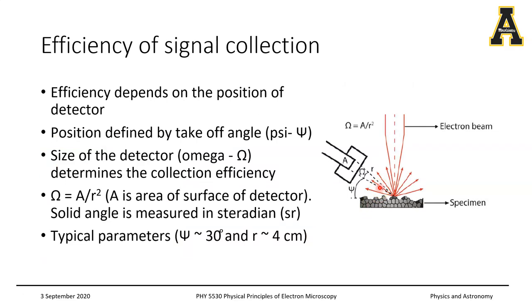Now let's look at the efficiency of signal collection. The tip of the ET detector is positioned at a takeoff angle psi, and the size of the detector is defined by omega, the solid angle subtended from the specimen. If the detector has area A and is placed at distance r, the solid angle is A/r² measured in steradians. Typically in an electron microscope with psi of 30 degrees and r of 4 centimeters, you get a pretty good collection of secondary electrons.